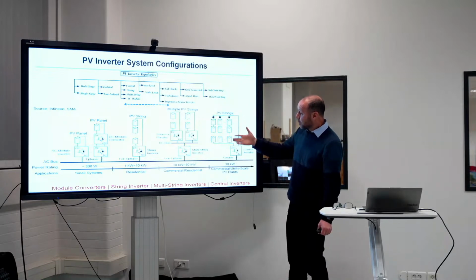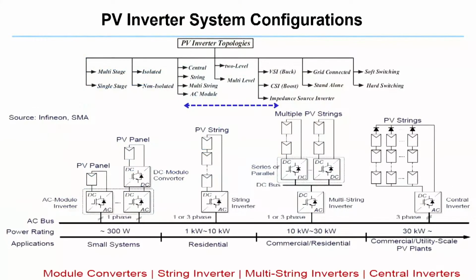Okay, the good thing about this first one is that you have a lower cost per watt, because in terms of cost, it's cheaper. But in terms of access to what happens at each string, you will have a problem. It means if this one here has maybe shading, it will impact the whole string. So actually you will have a drop at all these strings, so the amount of power will be less.